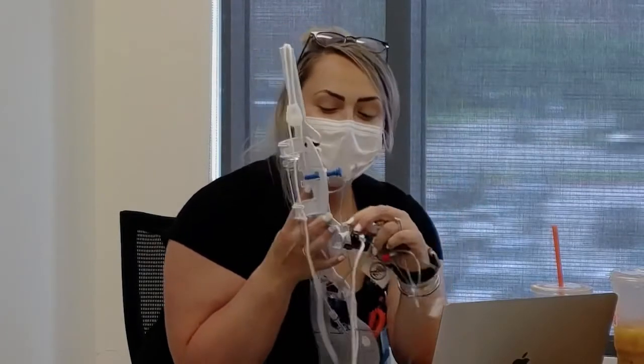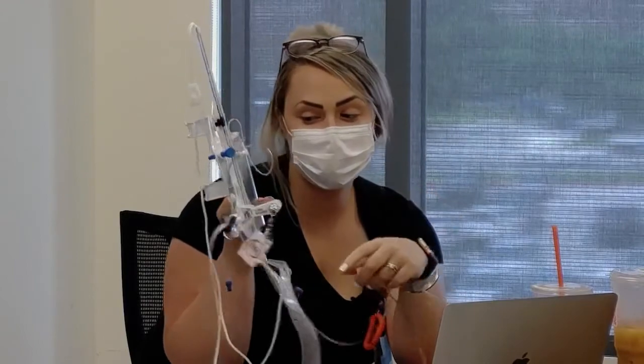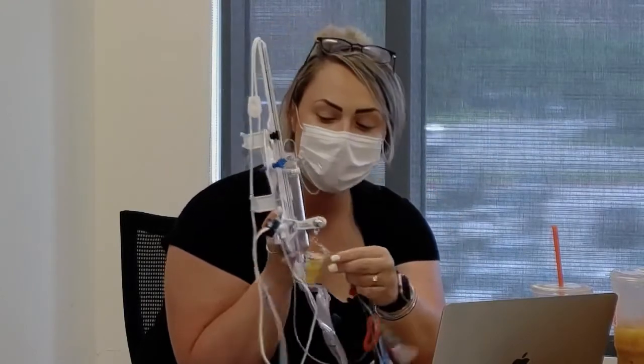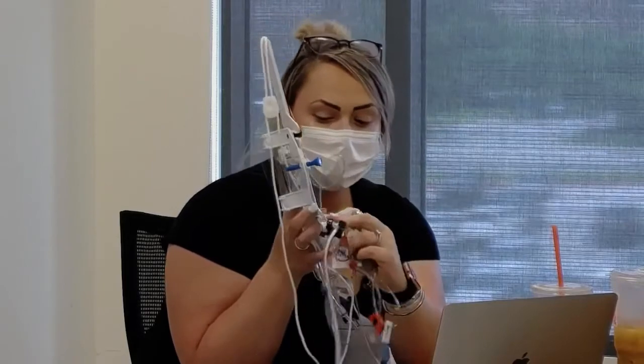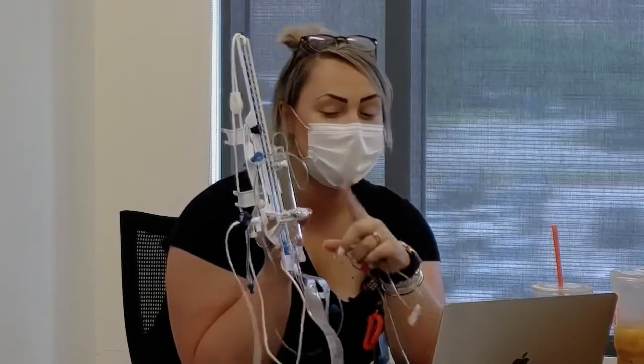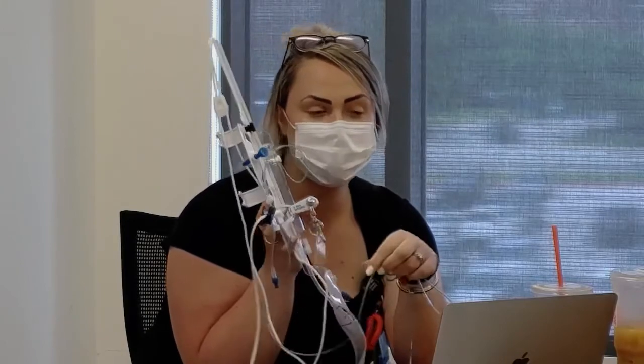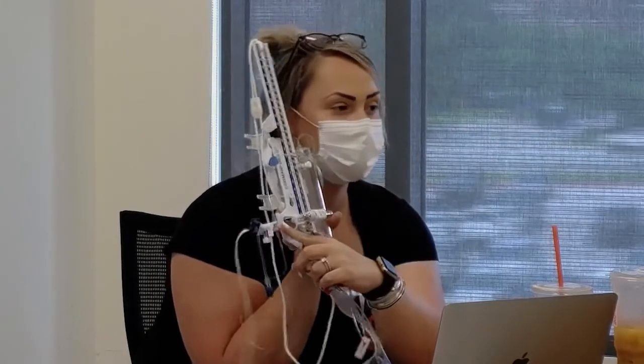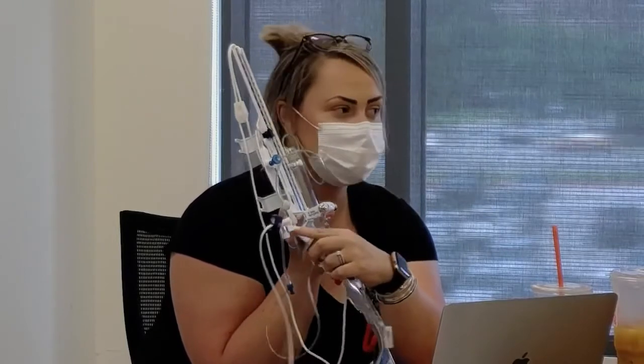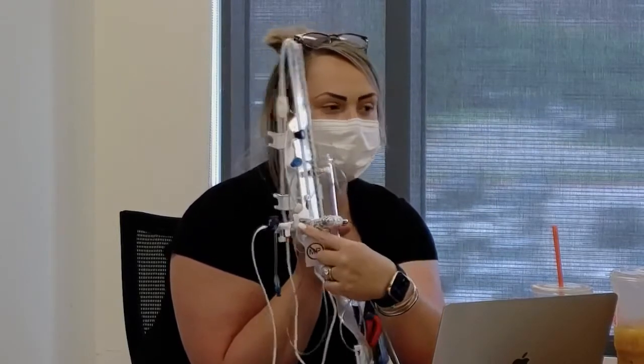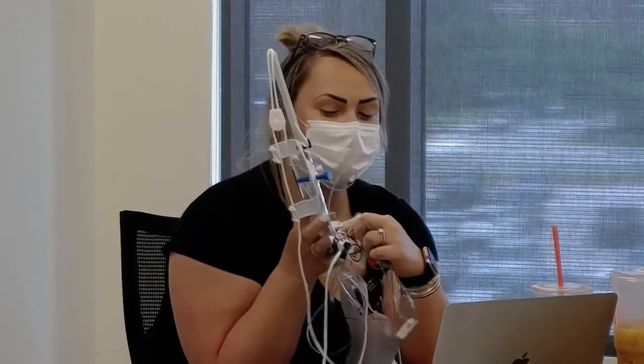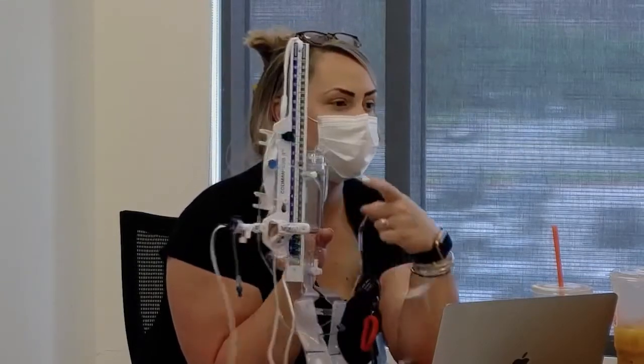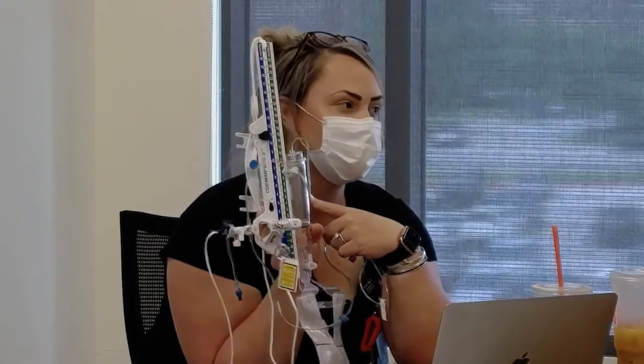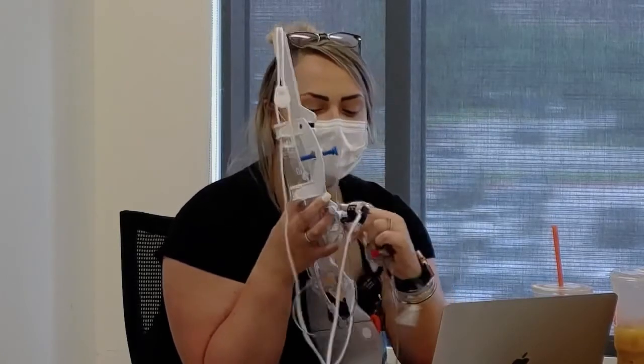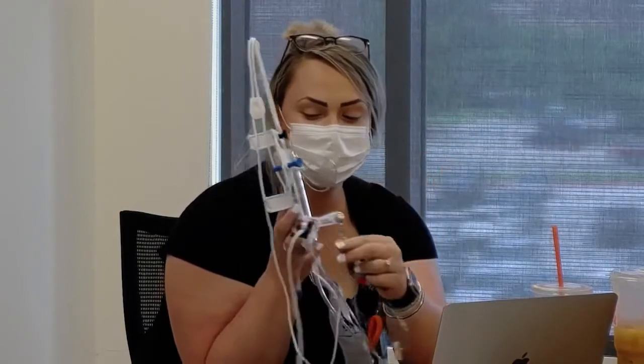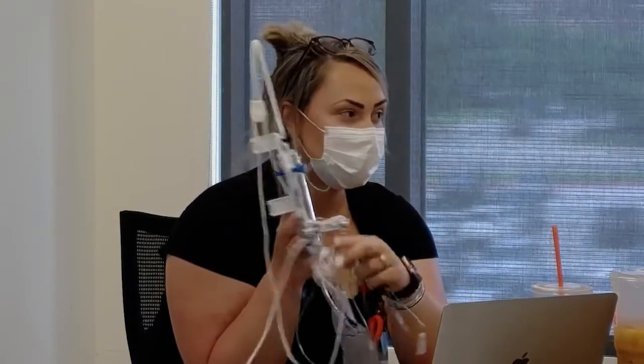To clamp, we can clamp up or we can clamp down. When we are leveling our system, we want to clamp up, and the reason we do that is because we want to be able to get our ICP. So we have it open to the transducer and open to the patient. When we're getting our ICP, we're clamping up. If we clamped down, we would get the pressure in the canister, which doesn't really help us, right? We want the patient's ICP.